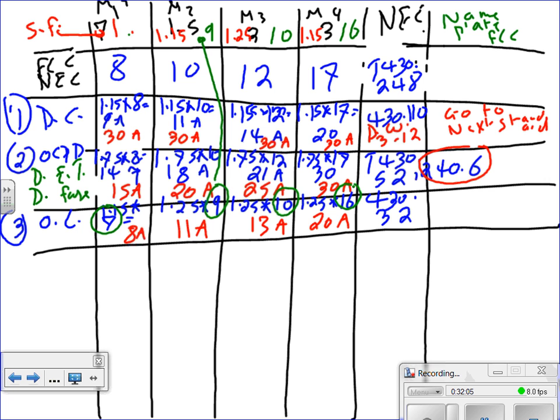Now, do you go up or down on these? You stay where you are. You adjust your electronic overload protection as close to 13 as you can get it. You don't go up and you don't go down. If I can't get it to be 13, what do you do? You go a little bit lower. You don't go even higher. So for all practical purposes, all we care about is just leaving it as is. So when Josh goes and sets the motor, go to the overload protection device over here and readjust it slightly until it fits the motor.